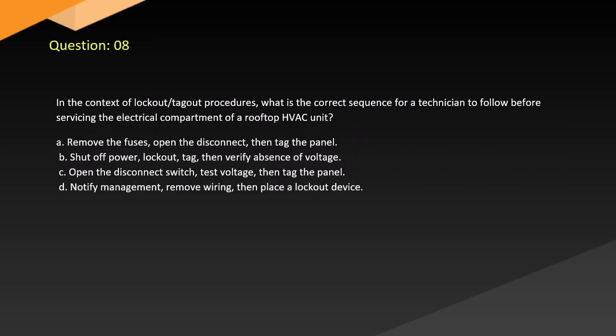Question 8. In the context of lockout-tagout procedures, what is the correct sequence for the technician to follow before servicing the electrical compartment of a rooftop HVAC unit? A. Remove the fuses, open the disconnect, then tag the panel. B. Shut off power, lockout tag, then verify absence of voltage. C. Open the disconnect switch, test voltage, then tag the panel. D. Notify management, remove wiring, then place a lockout device.